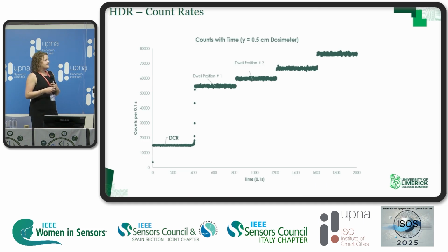So this takes an example of one of the sensor readings for the HDR system as the source is moving along the catheter towards the sensor, so as it gets closer. We initially have this dark count rate, and as the source is moving closer to that sensor, you see this increase in the signal that we're receiving. And so we're measuring these individual responses, and that will then give us the dose readings.